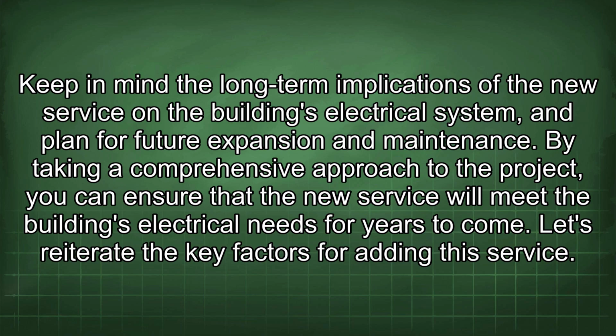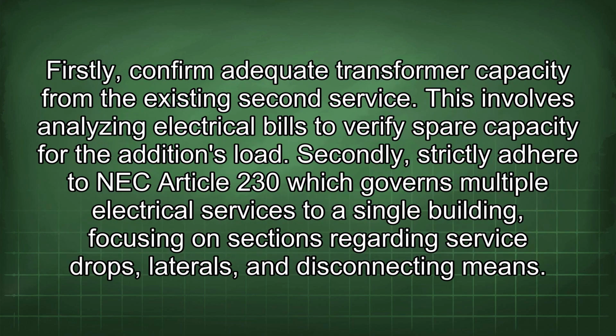Let's reiterate the key factors for adding this service. Firstly, confirm adequate transformer capacity from the existing second service. This involves analyzing electrical bills to verify spare capacity for the addition's load. Secondly, strictly adhere to NEC Article 230, which governs multiple electrical services to a single building, focusing on sections regarding service drops, laterals, and disconnecting means.